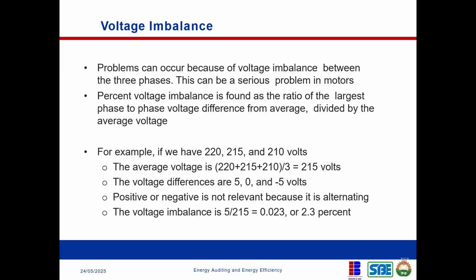The reason you get this voltage imbalance in some cases is because certain loads are concentrated on one line. That's why this matters for people in the electricity distribution business — they want to ensure none of their phases are overloaded at any point. For example, if your red phase is overloaded, that means more loss, because overloading causes higher heating on the cable, resulting in higher technical losses and power loss along the distribution network.